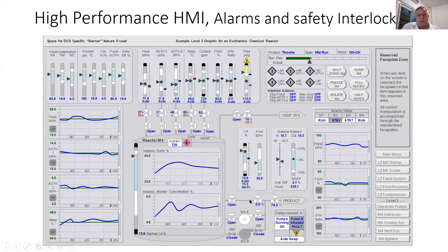But the developers of this high performance HMI point out that everything that is light or bright or just white is like a lamp. So if you switch on a lamp, it is light. If you switch off, it is dark. That is by their meaning. But the other people, and I also like to follow this way, say if that is gray, that means it has the same color as the pipe, so everything can go through. And if that is white, there is an interruption. So that means there is no connection from here to here. So there is a philosophy which is not clear, but by definition you can set in your project what is the meaning of white and gray. And then you should keep it, of course, over all your systems in your plant if you have several ones.